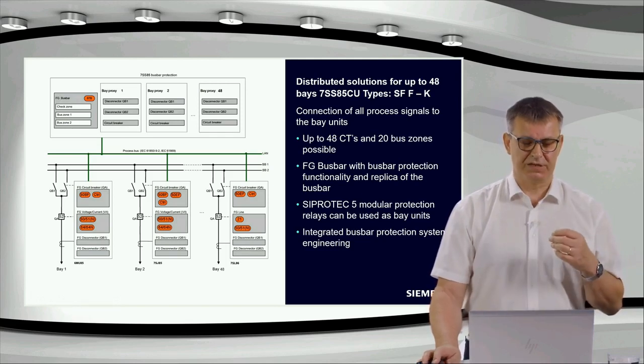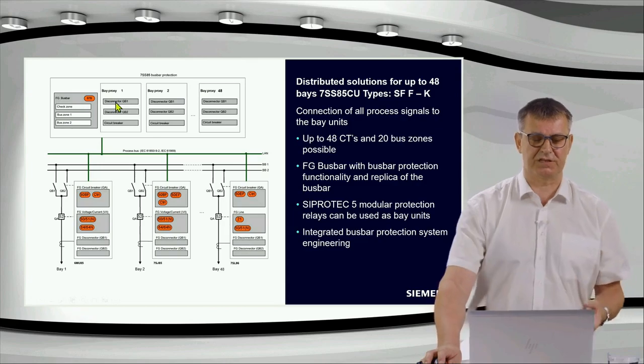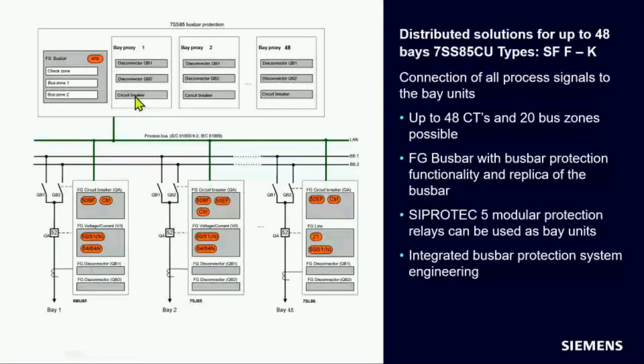We will have signals for the position of the disconnectors, signals of the position of the circuit breaker, of a retrip T1, of a retrip T2, versus the end-fault protection. So really much smaller, not so much memory consuming functionality inside the bay. Important is also that during this integrated busbar protection system engineering, all these proxies will be automatically created. This will Nina in her demonstration show later.